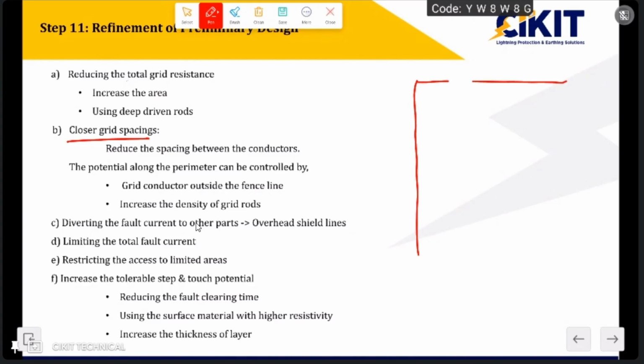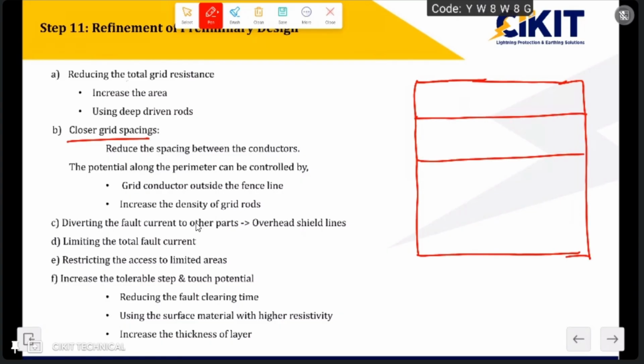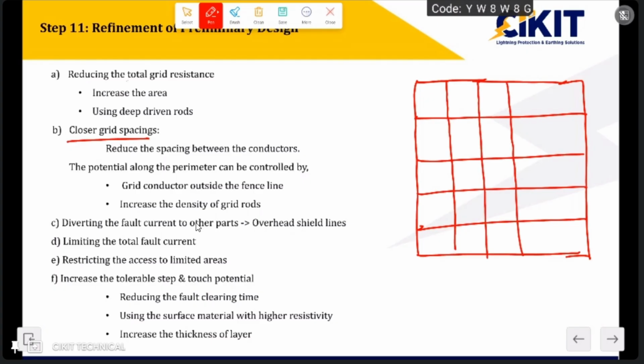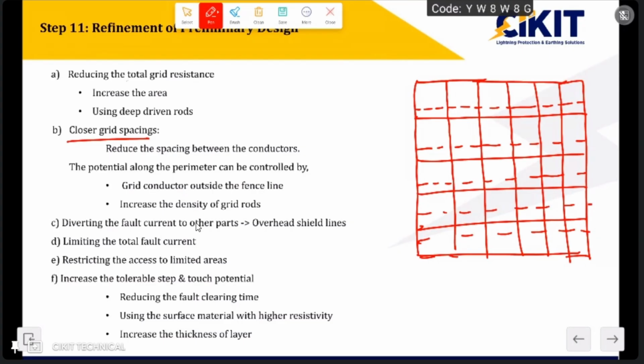So another option for reducing this RG value is by providing closer spacings. If in the initial case I'm having a spacing of around 5 meters, and the value I'm calculating is still higher, then instead of 5 meters, I can reduce the spacing. If I'm reducing the spacing, the conductors required will be higher. If the required conductor is increasing, then obviously the resistance will get reduced. So this is another option for reducing this RG value. By reducing the spacing, I can maintain the step and touch voltages within the limit inside this substation.